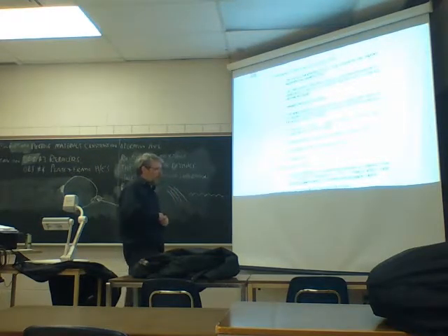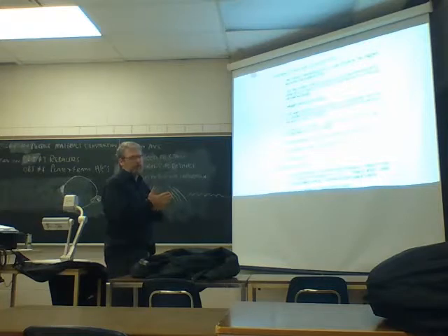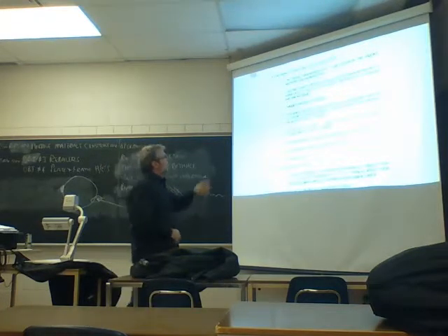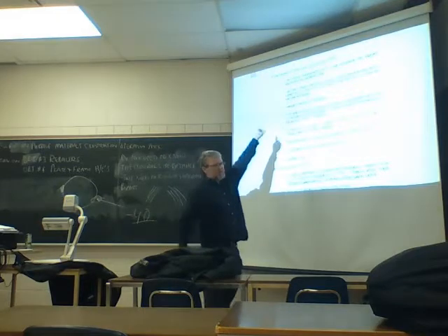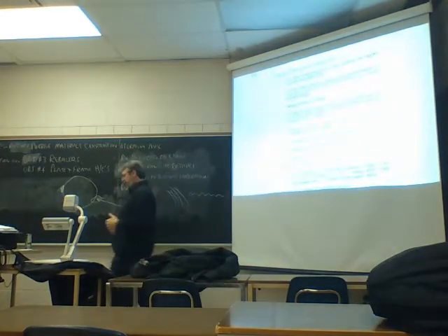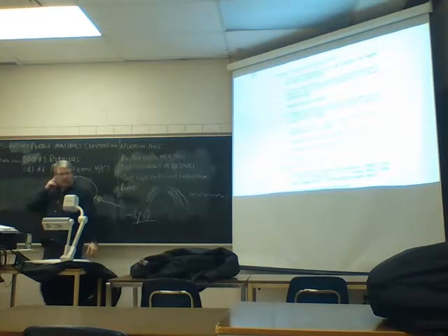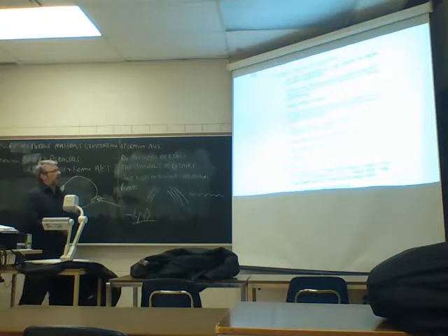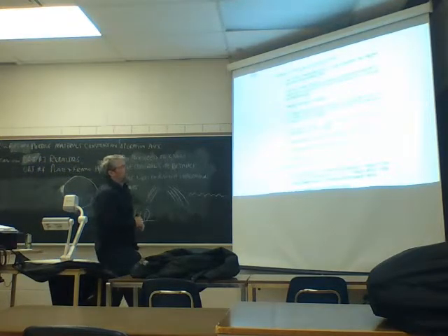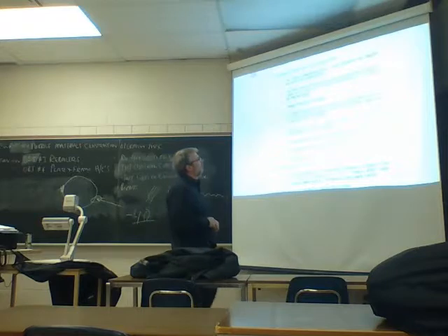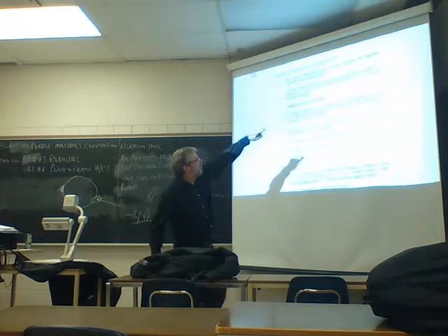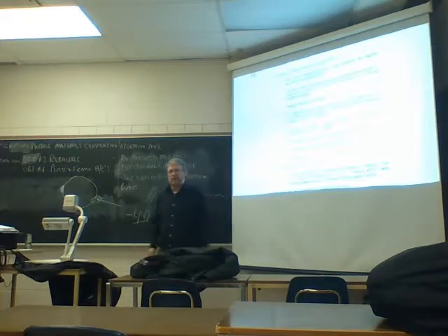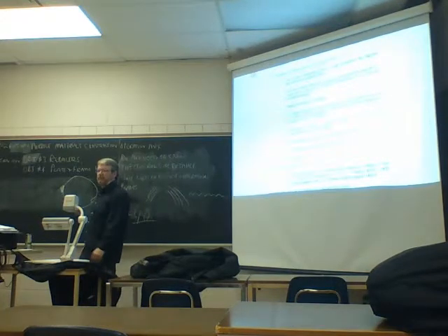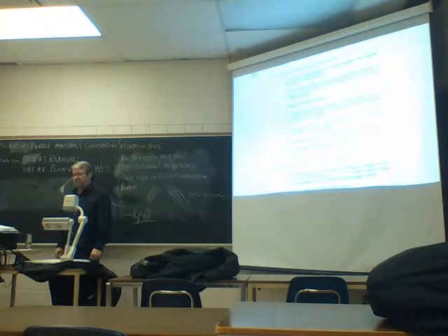Number two is what I just described to you as far as a plate and frame heat exchanger replacing a very large heat exchanger. High heat transfer coefficient reducing the surface area required for a given duty, 1/3 to 1/2 of that required for a tube and shell or shell and tube heat exchanger. I think in some cases it's actually more than that.